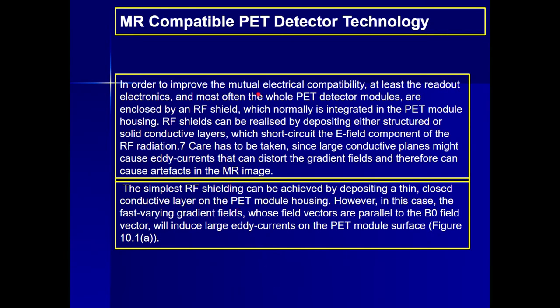In order to improve the mutual electrical compatibility, at least the readout electronics and most often the whole PET detector modules are enclosed by an RF shield, which normally is integrated in the PET module housing. RF shields can be realized by depositing either structured or solid conductive layers which short circuit the E field component of the RF radiation. Care has to be taken since large conductive planes might cause eddy currents that can distort the gradient fields and therefore can cause artifacts in the MR image.